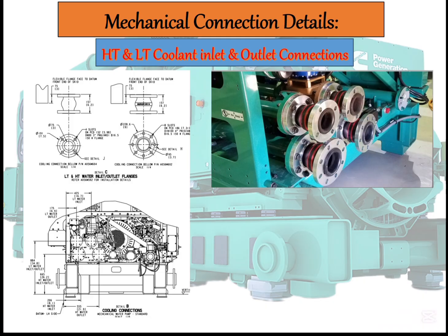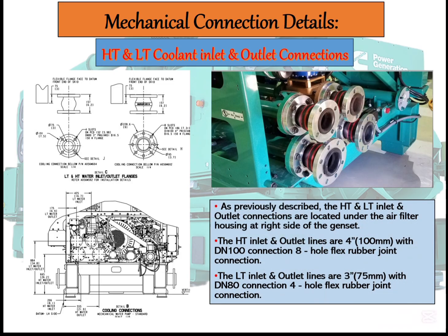This is the full diagram of the connections. Then the HT inlet and outlet line is 4-inch DN100, or 100 mm, with a flex rubber joint. The LT line is 3-inch, DN80 flanges. So from here we pick the lines to our cooling system. The cooling system depends on the area, whether it is a radiator or a cooling tower system. We will also look at this in the coming slides.